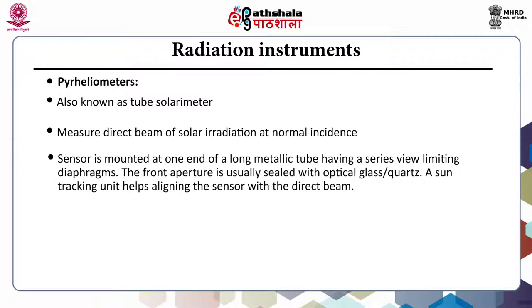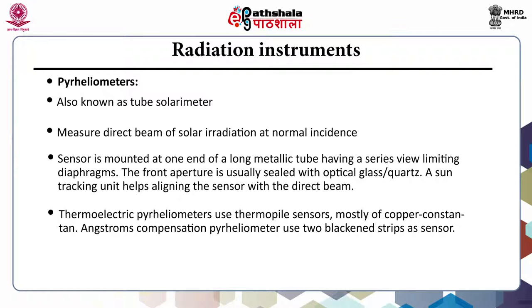Radiation instruments are generally referred to as radiometers. The first is pyrheliometer, which is meant for measurement of direct solar radiation of the sun — also known as a tube solarimeter. The sensor is mounted at one end of a long metallic tube having a series of view-limiting diaphragms, with the front aperture sealed with optical glass or quartz, and a sun tracking unit aligns the sensor with the direct beam. There are two types: thermoelectric type pyrheliometers, which use thermopile sensors mostly made of copper-constantan, and the Angstrom compensation pyrheliometer, which uses two blackened strips as sensors.